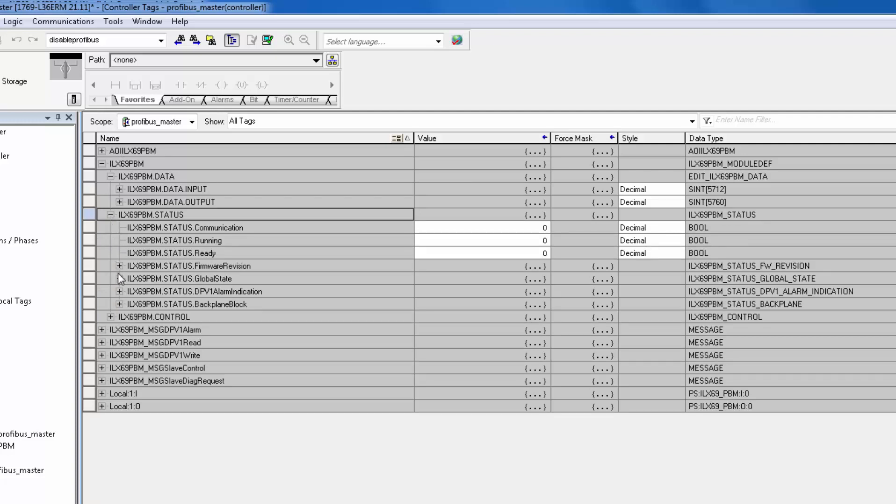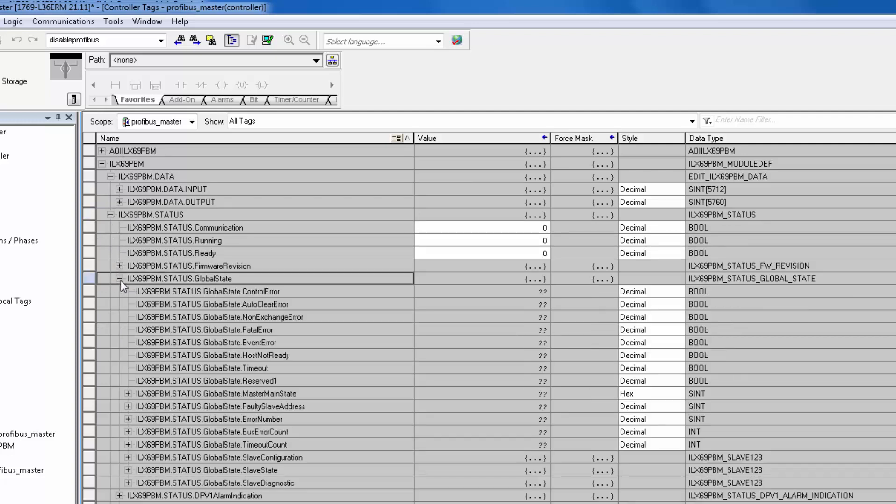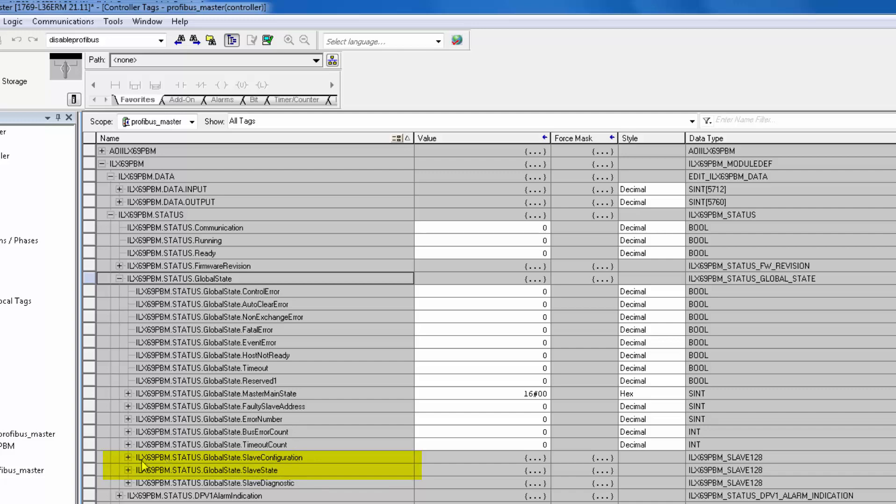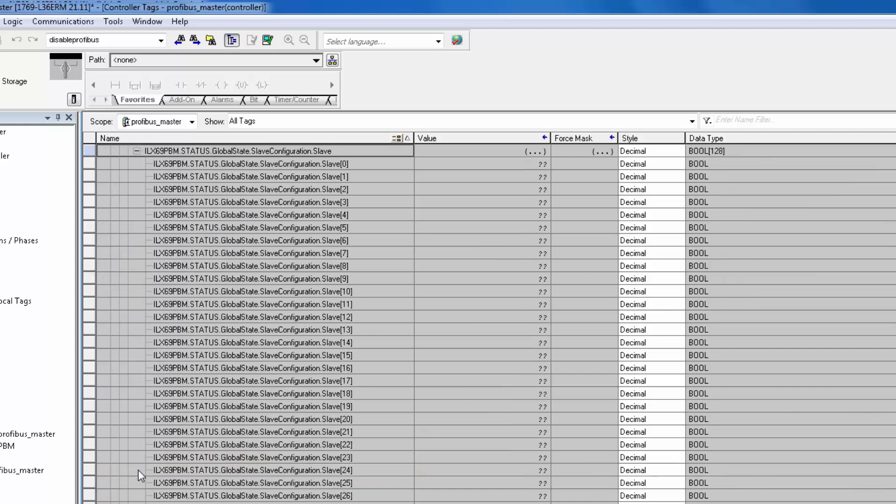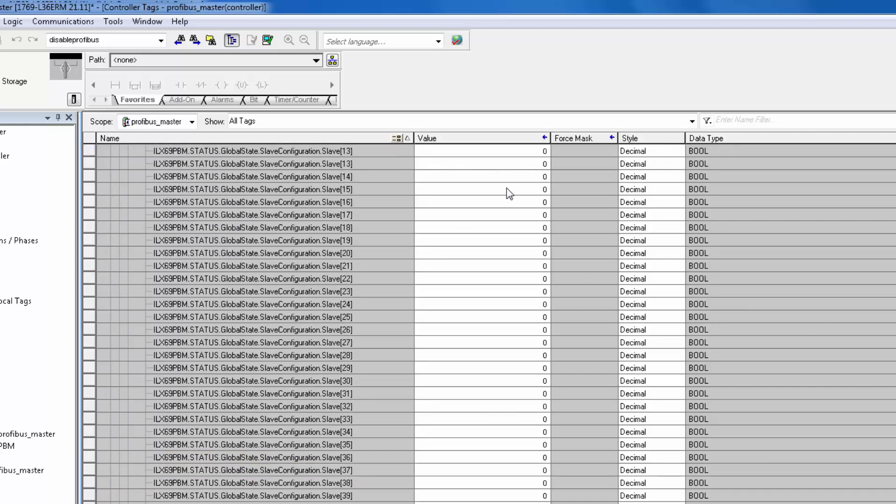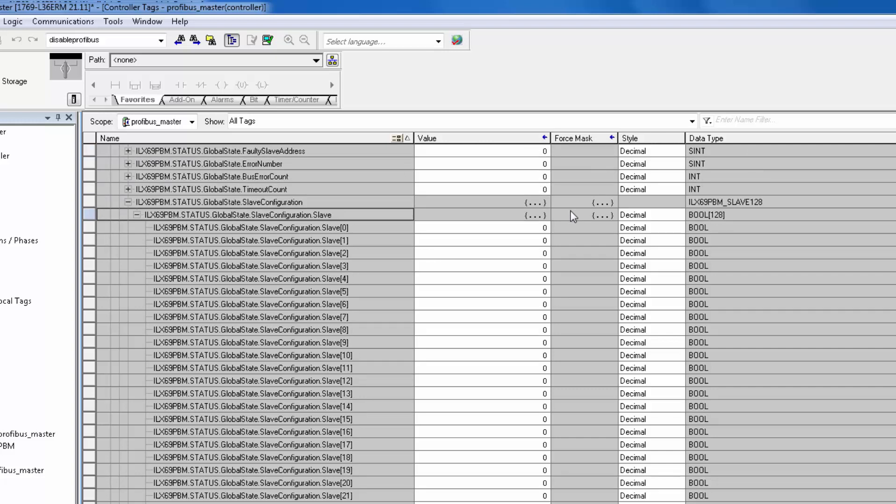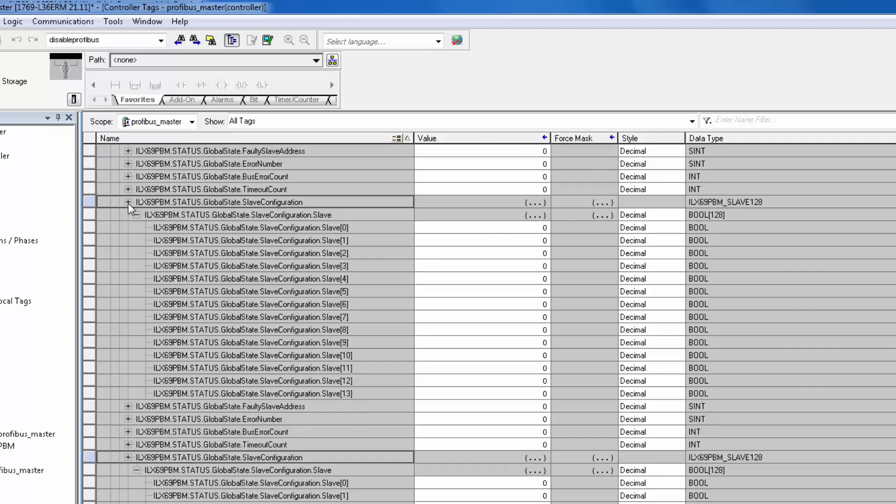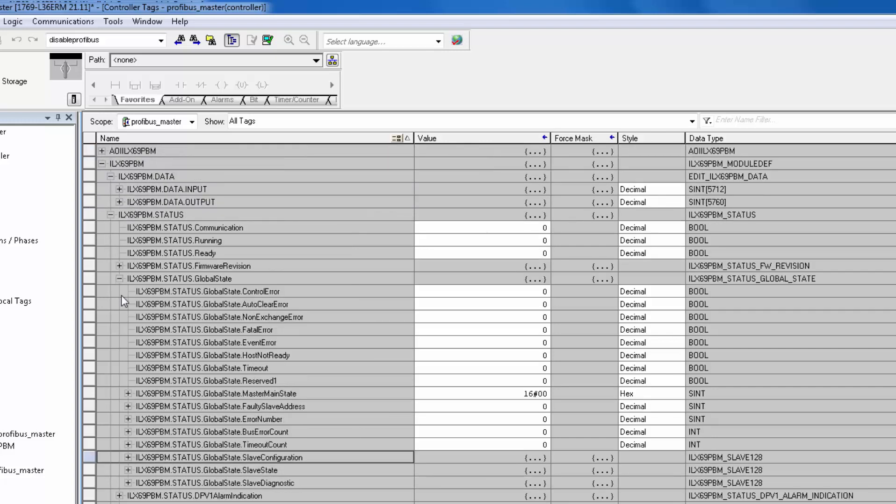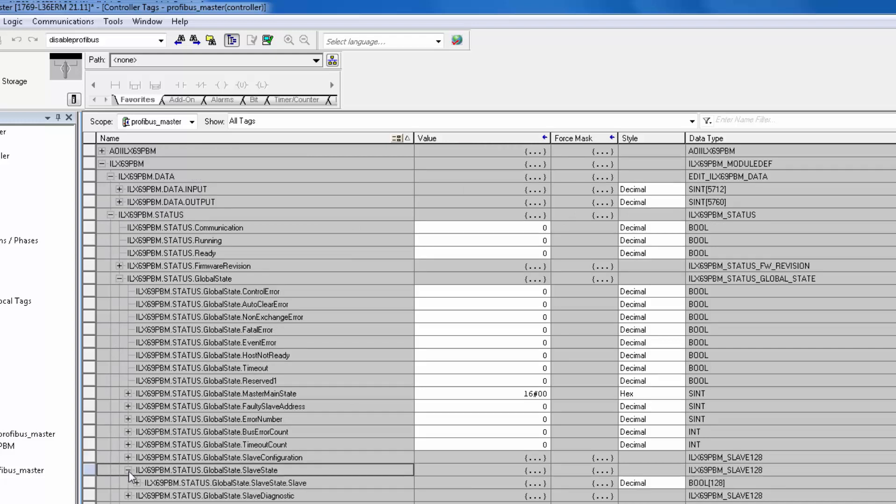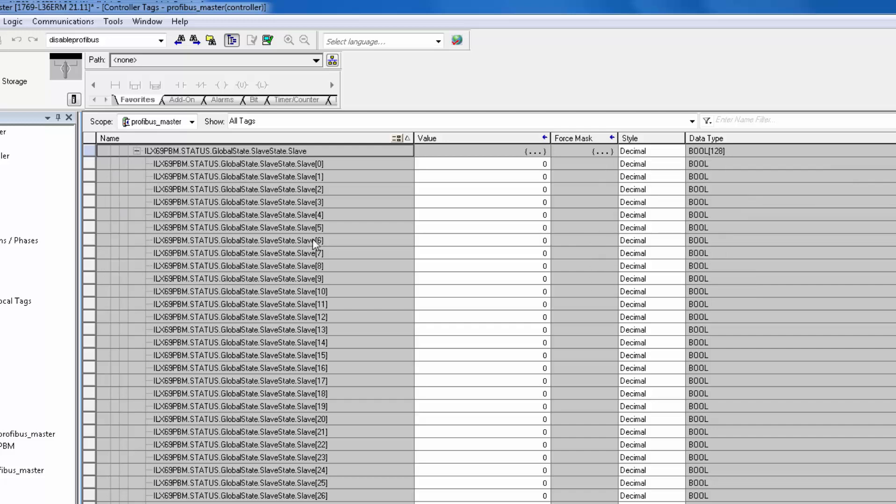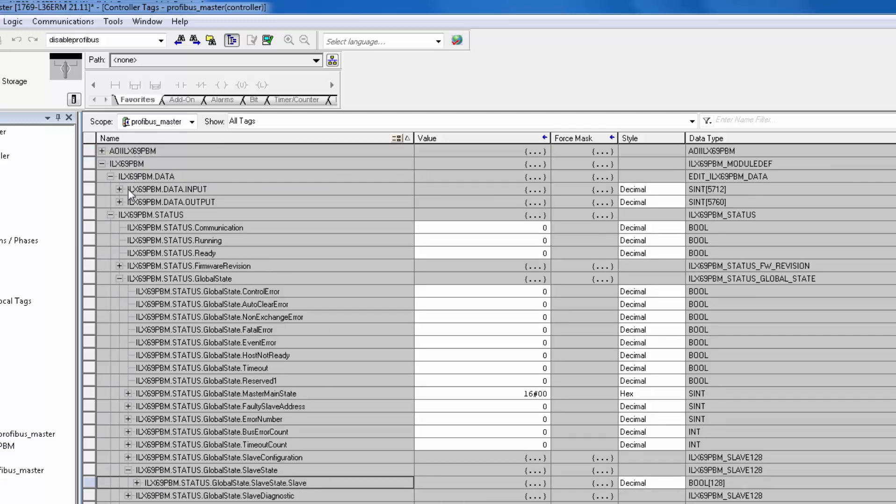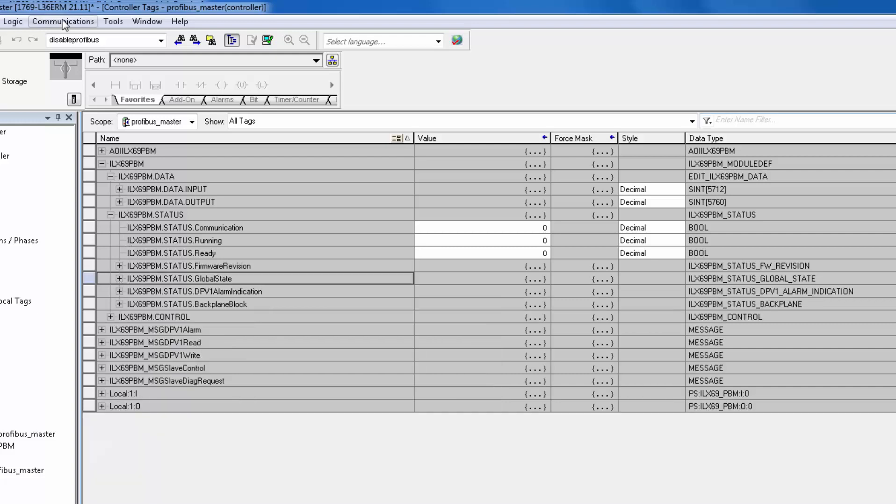Expand Global State, and you will find Slave Configured and Slave State. Slave Configured shows you what slaves you have configured with a 1 in the appropriate slave number. Slave State is a 1 for each of those slaves communicating. For my project, I will have a 1 in the 5th register for Slave 5 is configured and Slave 5 is communicating. Both of these arrays should match up. If not, you may have one or many slaves configured and not communicating. With that, we are done with Studio 5000.